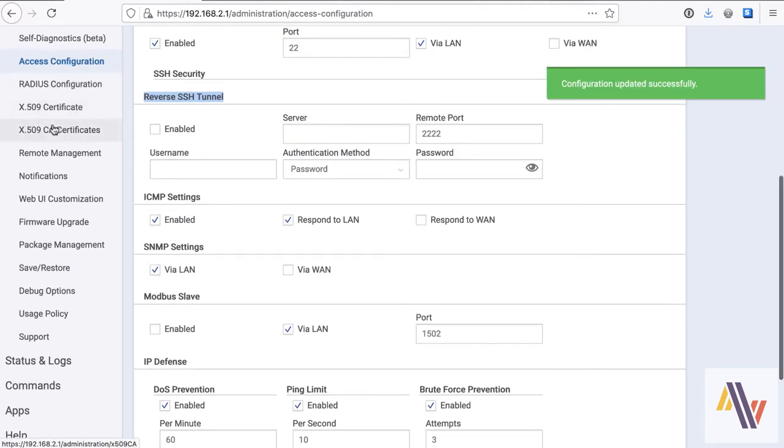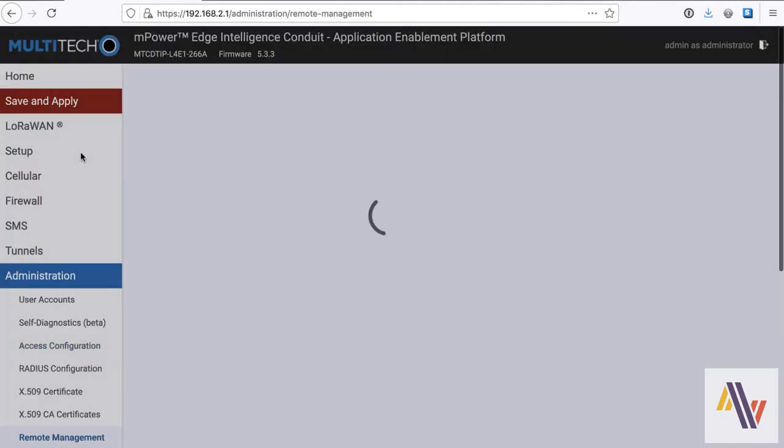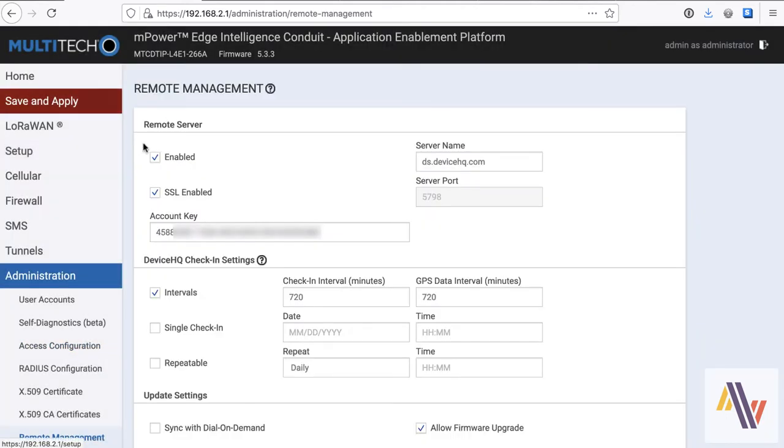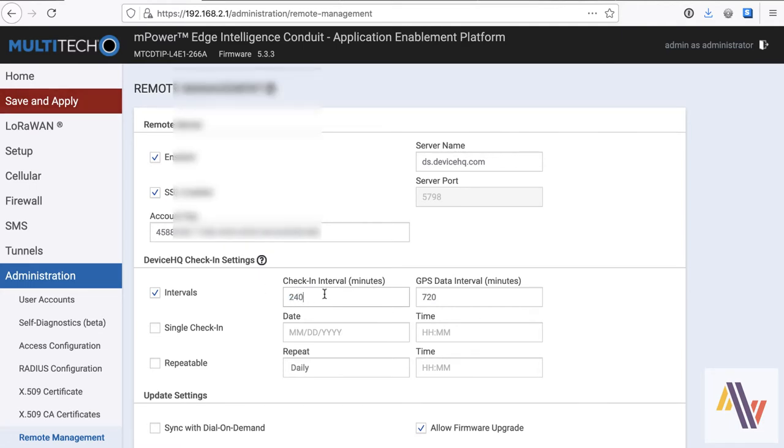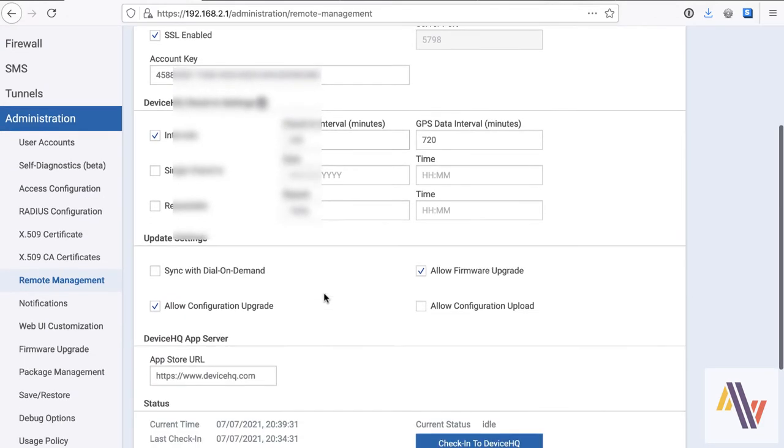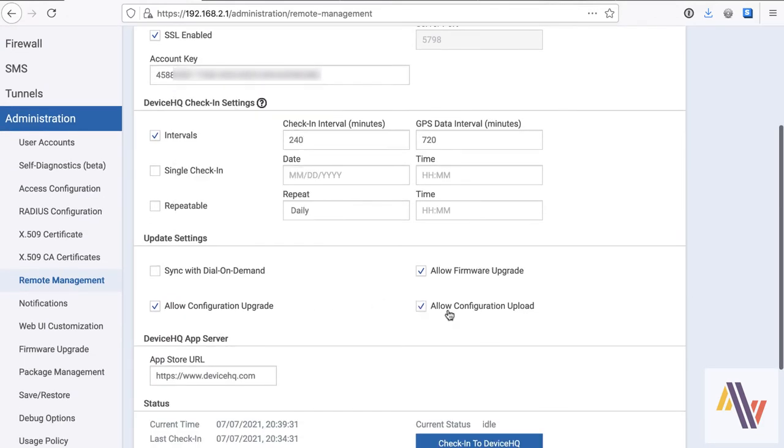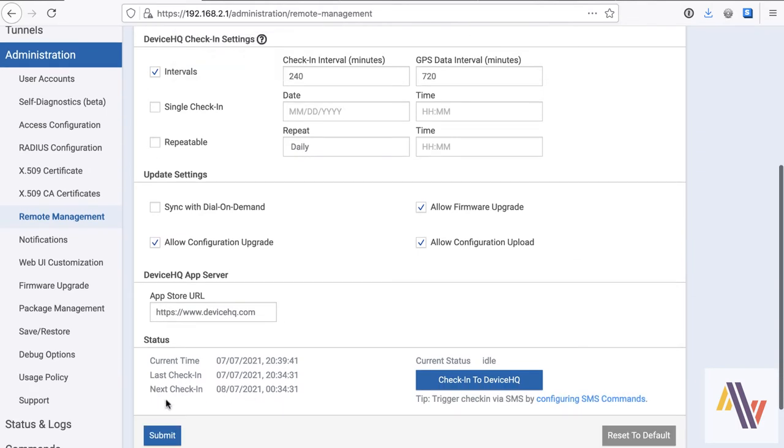On the remote management side, this is essentially the connection to DeviceHQ. This is enabled as we did it earlier over SSL, and here's our account key. I like to change the check-in interval to about four hours when setting these up. That's the minimum, by the way, just so that it checks in more often, but you can change that as necessary. And finally, I like to again allow configuration upload from here.